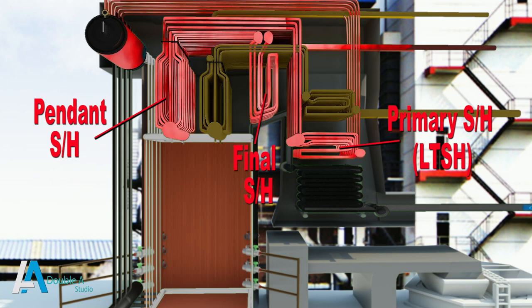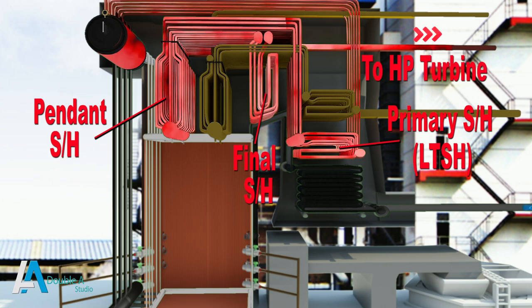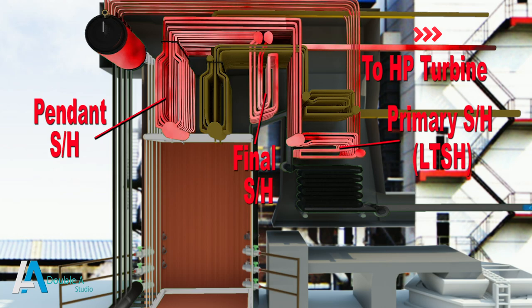When steam is heated up in the final superheater, the superheated steam is sent to the high pressure turbine for rotating the turbine blades. Thus, superheaters increase the enthalpy of steam, which increases work output in the turbine. They also recover heat from flue gases and increase the efficiency of the boiler.